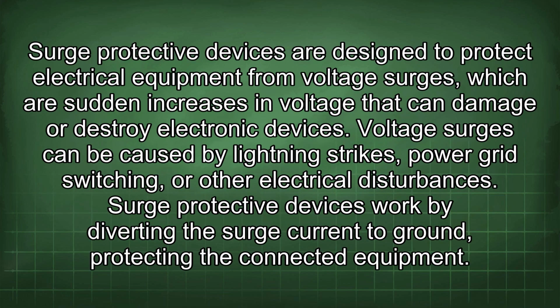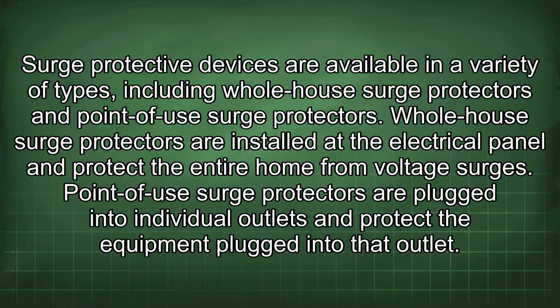Surge protective devices are designed to protect electrical equipment from voltage surges, which are sudden increases in voltage that can damage or destroy electronic devices. Voltage surges can be caused by lightning strikes, power grid switching, or other electrical disturbances. Surge protective devices work by diverting the surge current to ground, protecting the connected equipment. Surge protective devices are available in a variety of types, including whole-house surge protectors and point-of-use surge protectors.